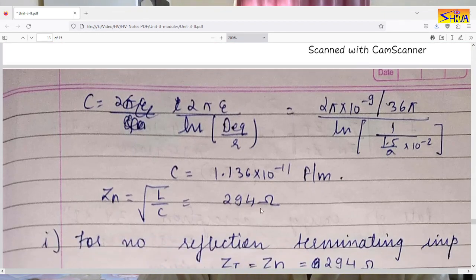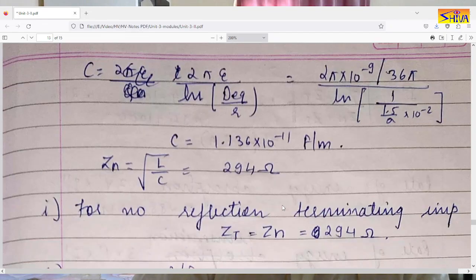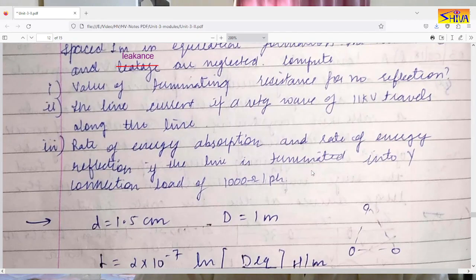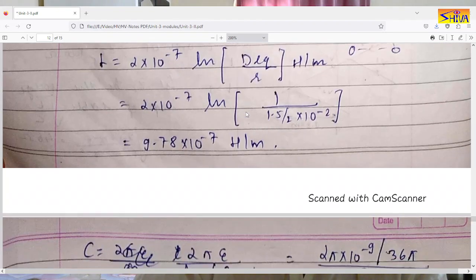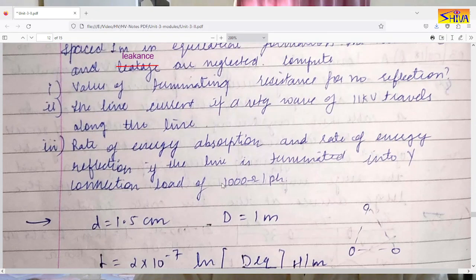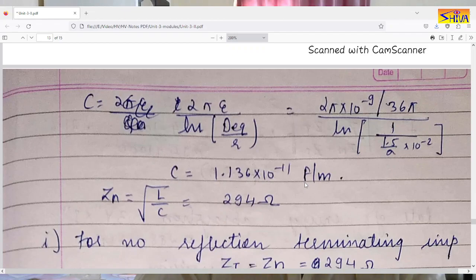The surge impedance Zn = √(L/C) = 294 ohms. For no reflection, the terminating impedance Zt must equal Zn, so Zt = 294 ohms. For part two, the line current equals the phase voltage divided by the surge impedance: (11 kV / √3) / 294 = 21.6 amperes.